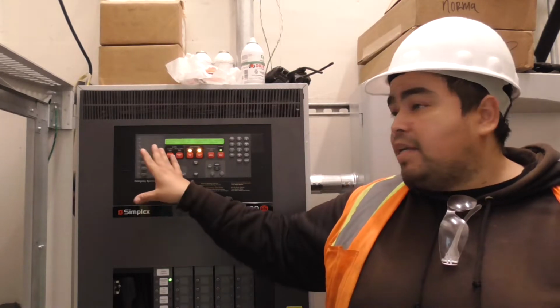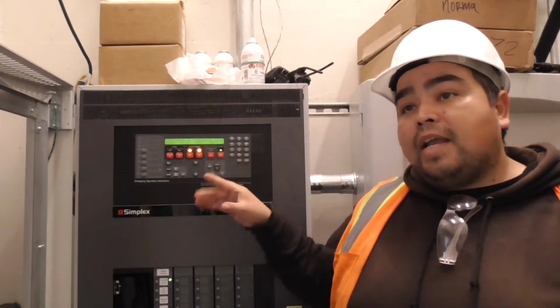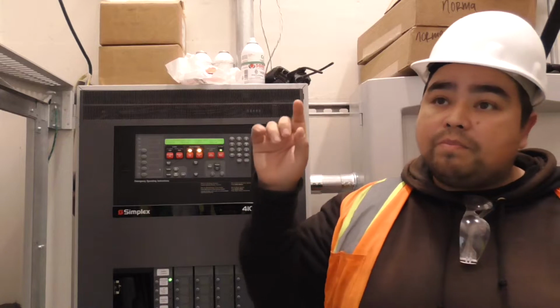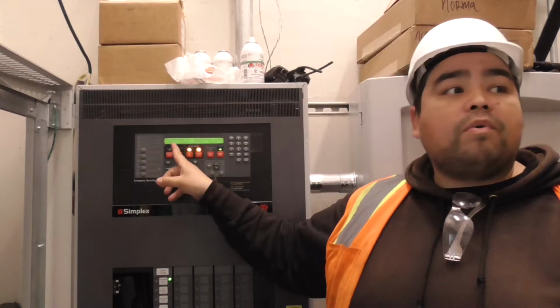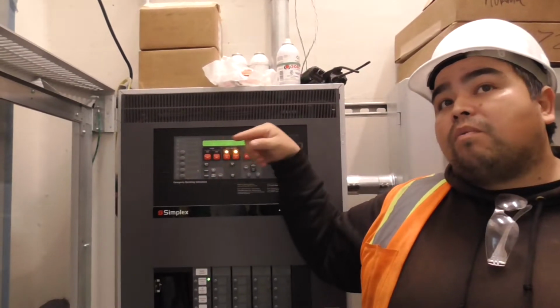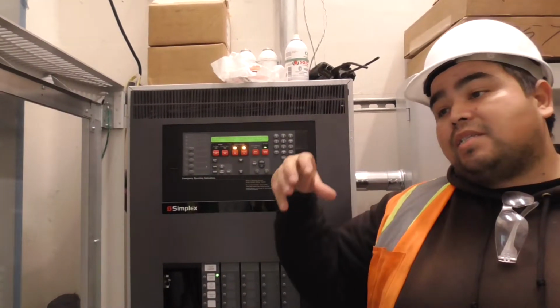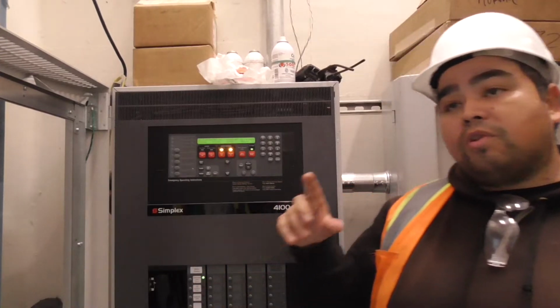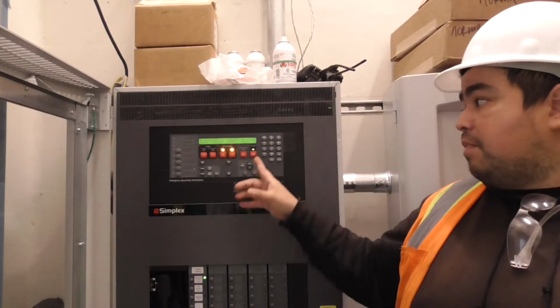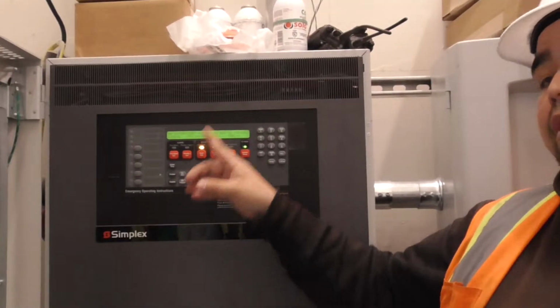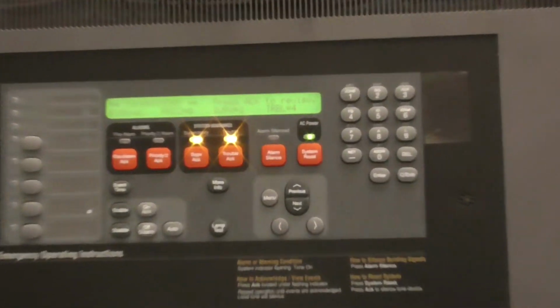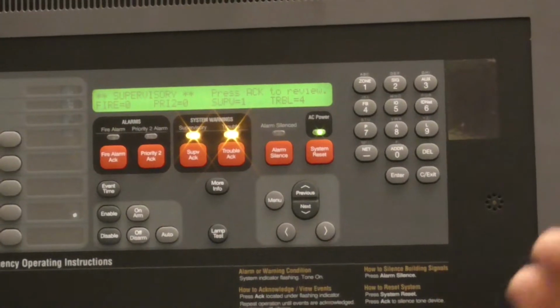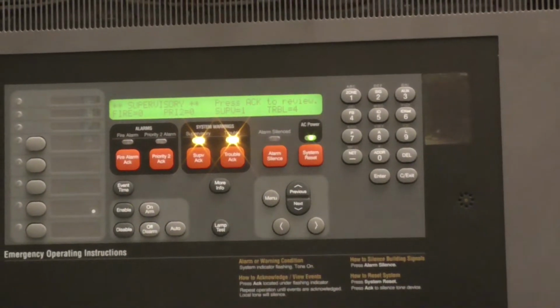Now, if I leave that condition and don't reset the panel, and I go and respray the same device and put it back in alarm, it'll flash red again at me, letting me know it went back under detection, but it will not set the building off again because it's the same device. The only way to get it to set the building off again is by resetting it, so it clears, and then putting it back into alarm. It's important to reset. It's the same thing for the rooms. You need to make sure that you reset, otherwise you won't get a re-alarm on that device.